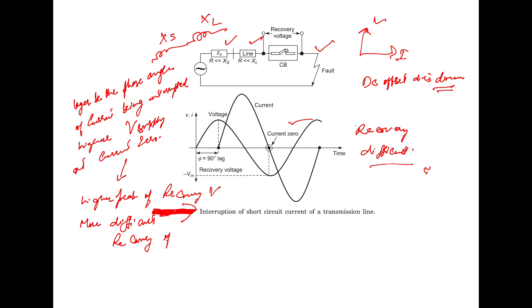Now we will discuss the effect of first pole to clear. In the three-phase system, the natural current zero instant in each phase does not occur simultaneously. These instants are shifted in time from each other because of the very nature of the three-phase system. As you know, the phases are 120 degrees apart. So it is natural that one of the poles of the three-phase circuit will clear the fault earlier than the other.